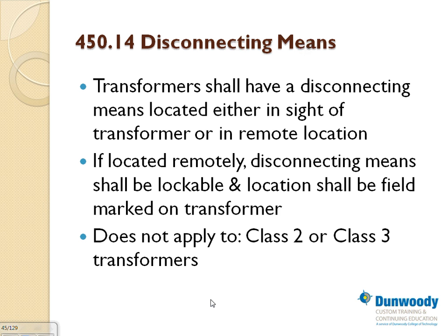In 2011 only, this is brand new, guys. In 2011, they came up and said you have to have a disconnect for the transformer. Before 2011, you did not need a disconnect for a transformer. Now, only in 2011, they require every transformer to have a disconnect. Now the disconnecting means must be within sight of the transformer, or if it's not within sight, it has to be able to be locked in the open position. You have to be able to lock that transformer disconnect in the open position. And if it's not within sight, you have to have a label right at the transformer to tell you the location of the disconnect for that transformer.